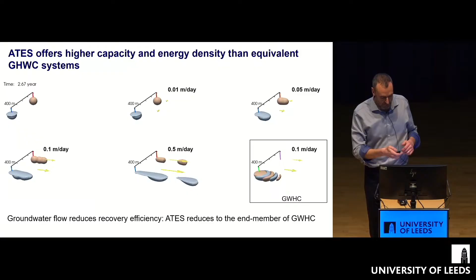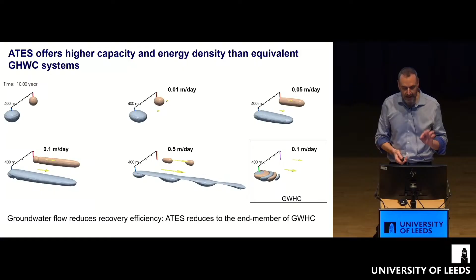One of the things we could also look at is groundwater flow. Fleur talked about that as being the enemy of storage, and I agree with her, it is, right? So here we're looking at different ATES systems with different groundwater flow rates - no groundwater flow and then increasing groundwater flow. You can see that does take the heat away from the ATES systems. If you have groundwater flow moving those plumes, you're going to get less of that back. But you have to get to relatively high flow rates before that really becomes a pain.